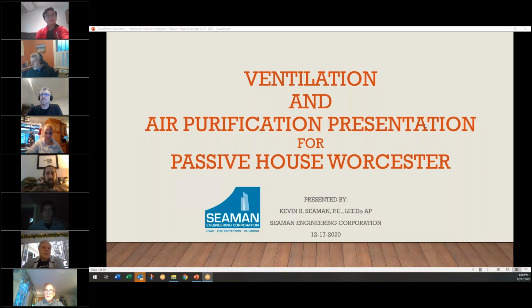like an afterthought. People would push, well, can we use natural ventilation? The code says we can use natural ventilation. We can just open a window, you know? And I'm like, well, you're really not guaranteeing you're getting ventilation by opening a window when it's January and making sure you get the right amount of air. So it's kind of helped in that regard to get people to understand that it's important to have a good mechanical system to allow the building they're in to breathe and to keep the quality right. So we can go to the next slide, Wes.